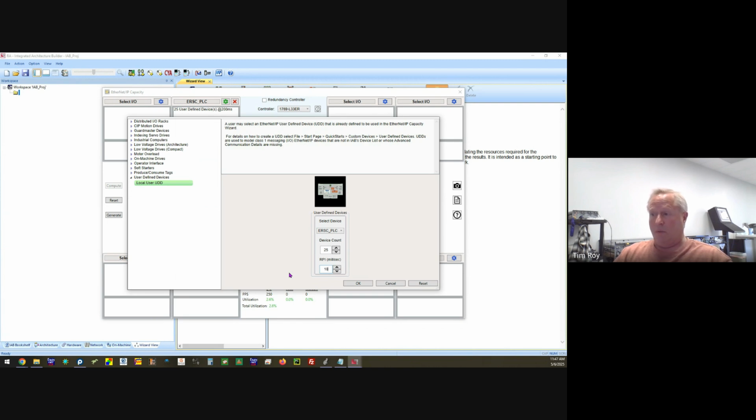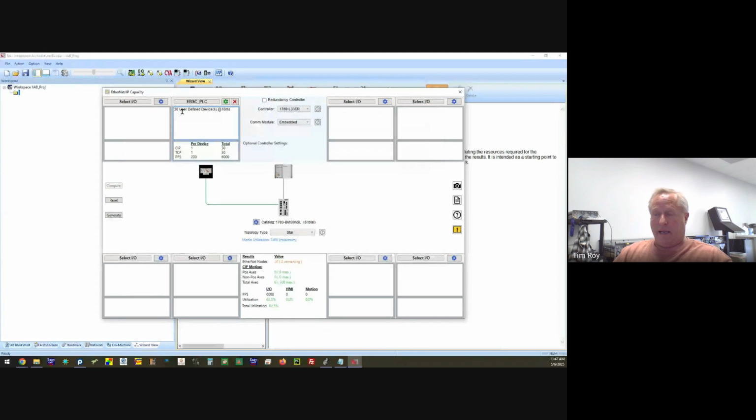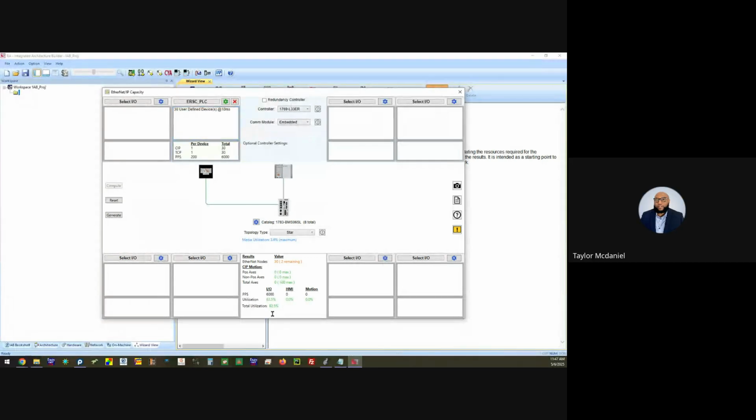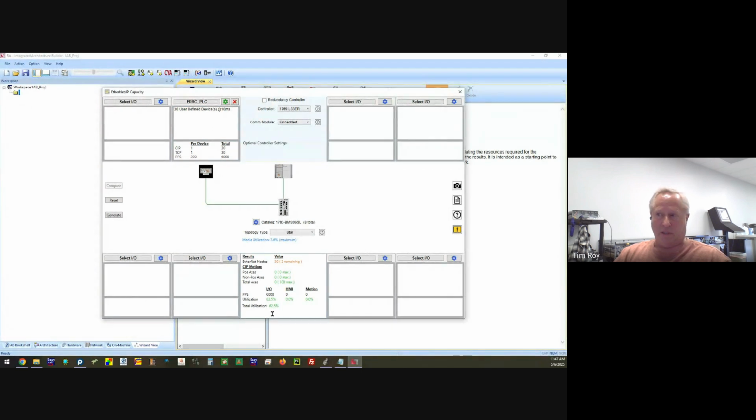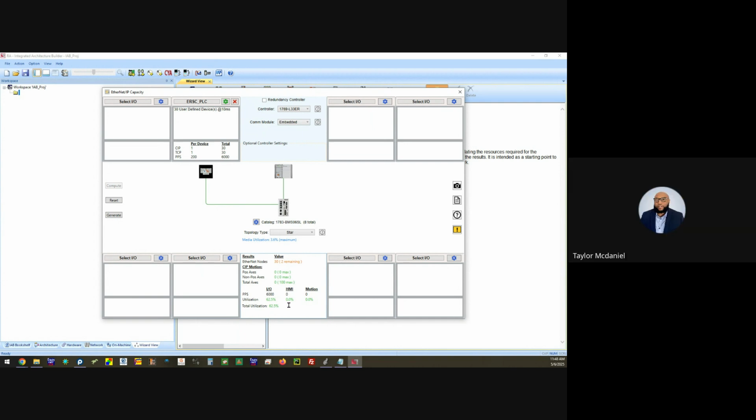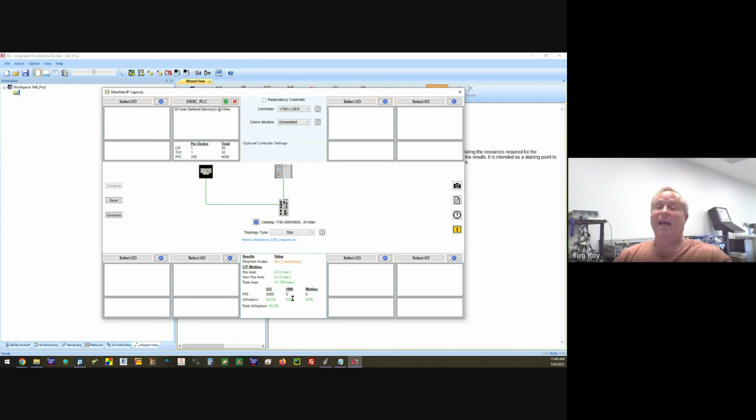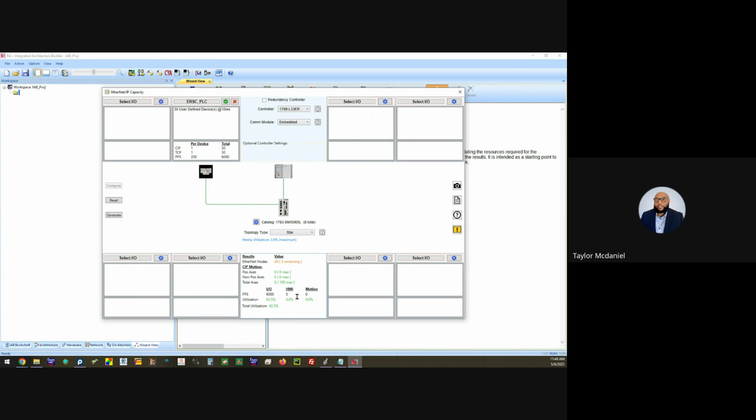Well, look at that. I added 5 more modules and cranked the RPI rate down to 10. Now I'm at 62% of utilization for the communications. So you can see that was just 5 modules, but cranking down the RPI, now the processor's using most of its time for communications. And you're polling at the same time, though. Yes. But if you staggered, you probably have an improved utilization.